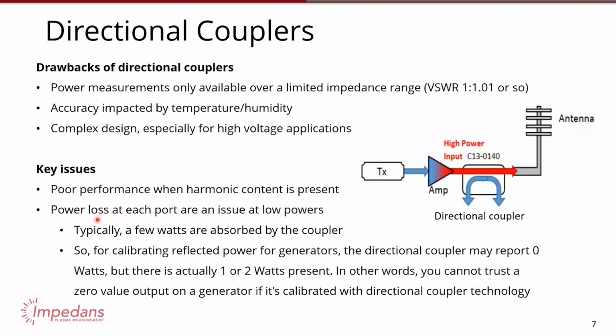And you also get power loss at the ports. So one thing to note if you're using this type of technology to calibrate a generator or something is that a few watts are absorbed by the coupler. So that means, if you calibrated a generator to the point where it says 0 watts according to your directional coupler, it's actually absorbing a couple of watts, so there's still some power.